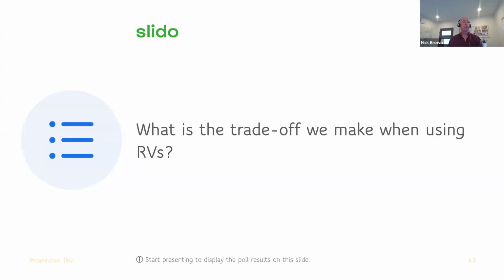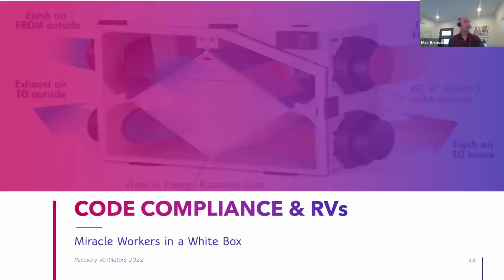All right, the trade-off I was looking for was we're going to use more energy to move more air and add a second fan for exhaust. But the heat exchanger core is going to temper the incoming fresh air, which will save us energy on our HVAC. Plus upfront cost versus cost per kWh, right? Yeah, valid point, George and Mark.